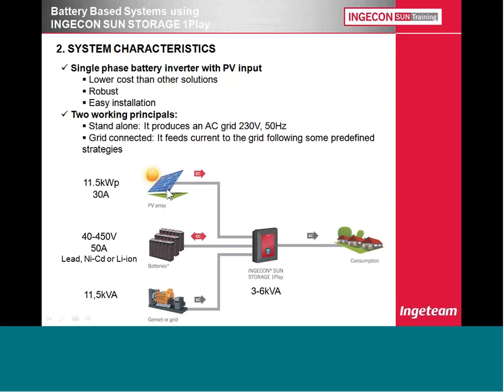Here, as you can see, these are the characteristics. I'm not going to enter much into this because this is all included in the data sheet of the inverter. These are the characteristics of a PV array you can connect to your inverter. You can go up to 11.5 kilowatts peak. You are able to take up to 30 amps from the PV modules. For batteries, these are the conditions: the voltage that we require from the batteries ranges from 40 to 450 volts. We're able to take up to 50 amps in both directions, from the batteries towards the inverter or the other way around.